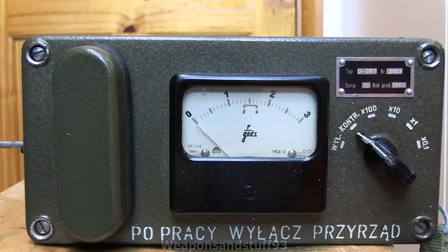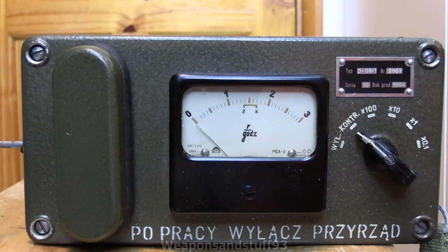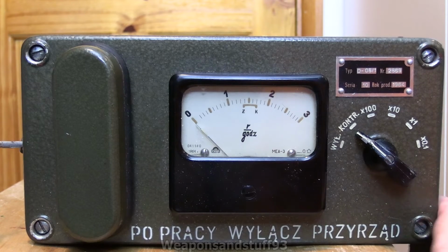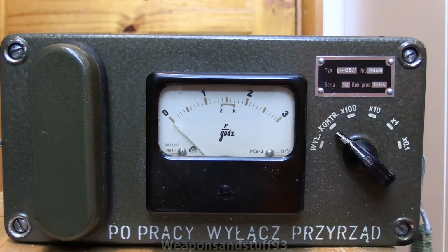Now, this is where sometimes you can't even get this to power on unless you leave it for a minute or two just sitting in there with the battery compartment closed, and it turned on. And sometimes I've noticed you have to turn all the calibration switches, and I don't know if this is just an age thing, all the way up. Once the calibration switches have gone all the way up, sometimes the meter powers on, and then you can adjust it to how you need it.